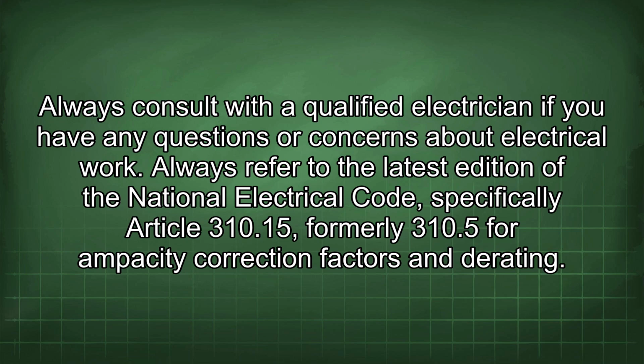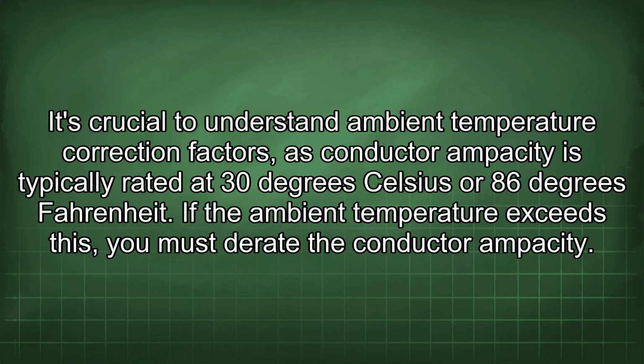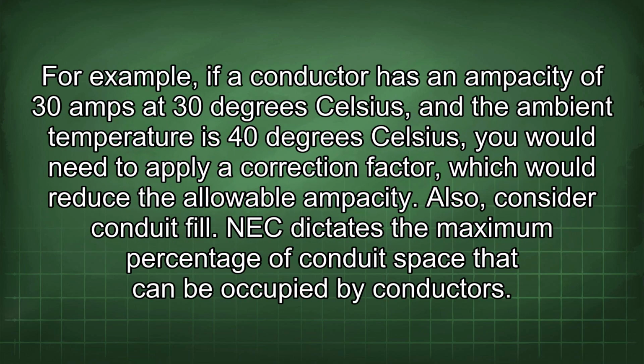Always refer to the latest edition of the National Electrical Code, specifically Article 310.15, formerly 310.5, for ampacity correction factors and derating. It's crucial to understand ambient temperature correction factors, as conductor ampacity is typically rated at 30 degrees Celsius or 86 degrees Fahrenheit. If the ambient temperature exceeds this, you must derate the conductor ampacity. For example, if a conductor has an ampacity of 30 amps at 30 degrees Celsius and the ambient temperature is 40 degrees Celsius, you would need to apply a correction factor, which would reduce the allowable ampacity.